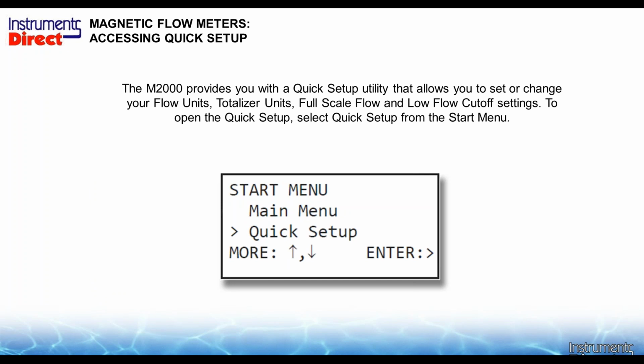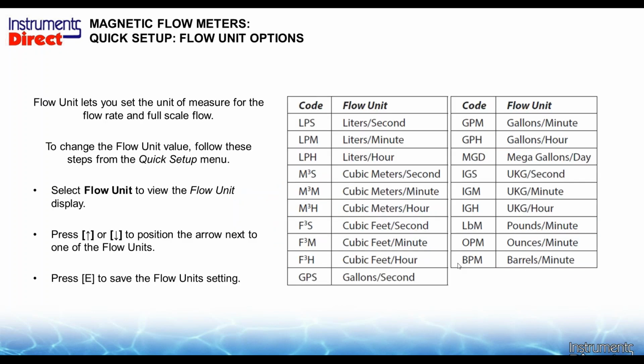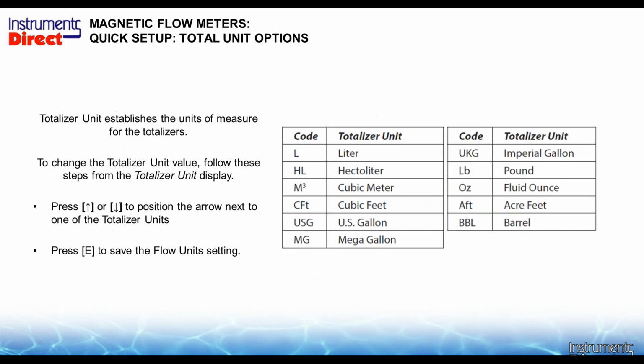But if you wanted to rescale your 4 to 20 milliamp output, or you wanted to change the engineering unit, then you would go to the quick start or the quick setup, hit the start menu there and enter. And this is where you can change the engineering units to liters from gallons or whatever else you wanted to do for flow rate there. And at the same token, if you wanted to change your totalization there, you wanted to go to pounds or you wanted to measure in barrels, this is where you could go and change your information again using the quick setup function. So very simple to do, not required in most installations.